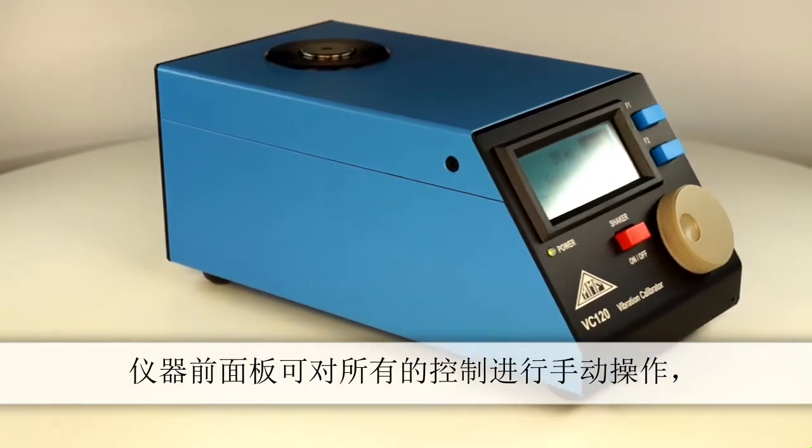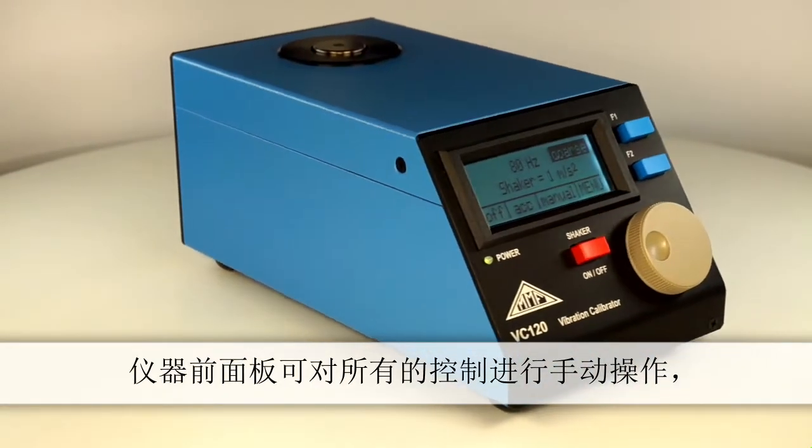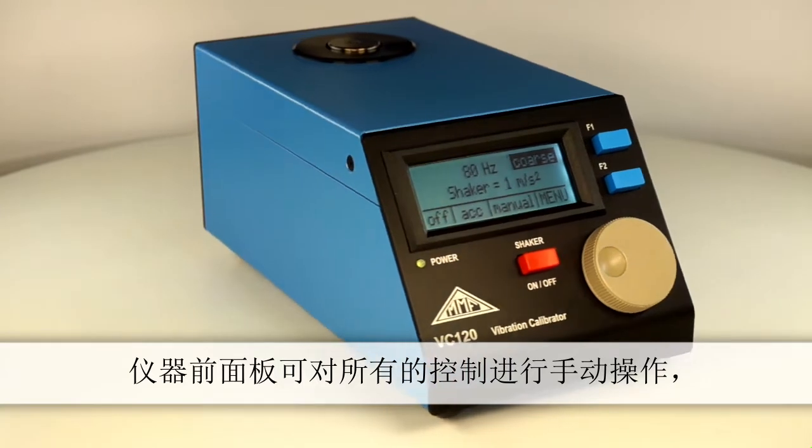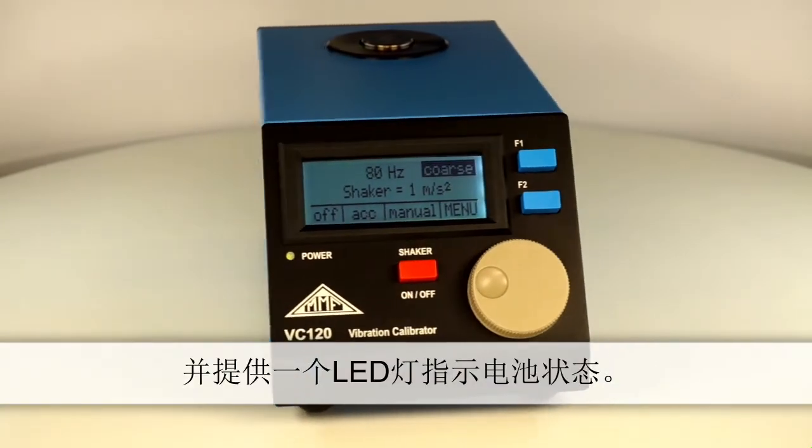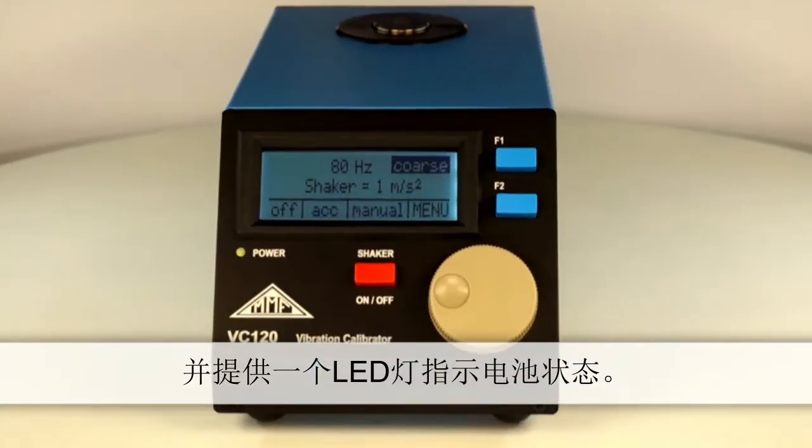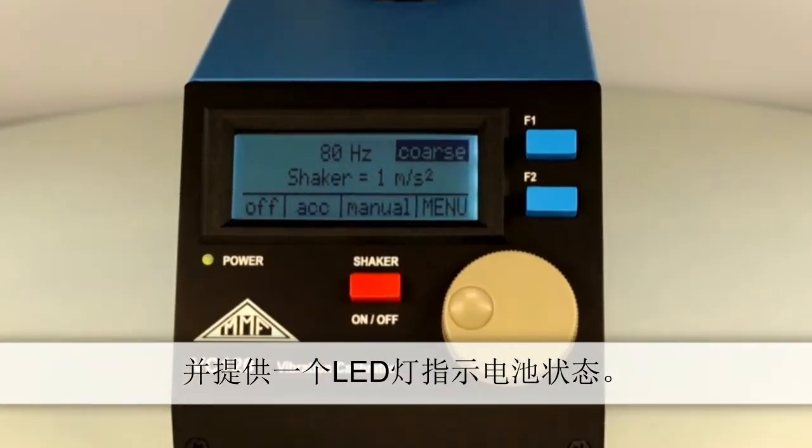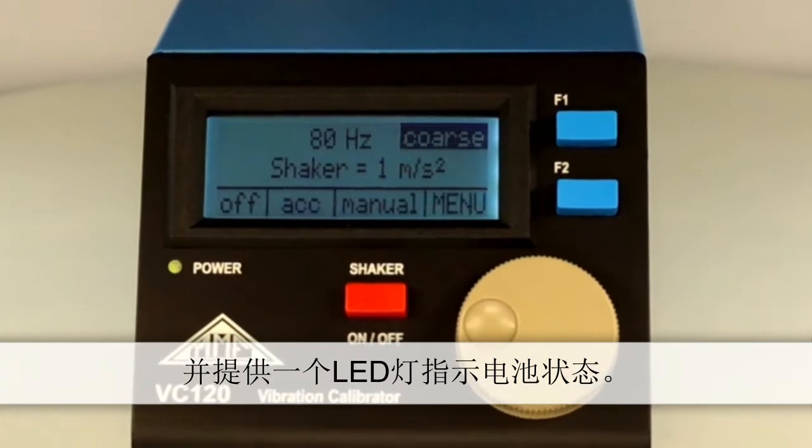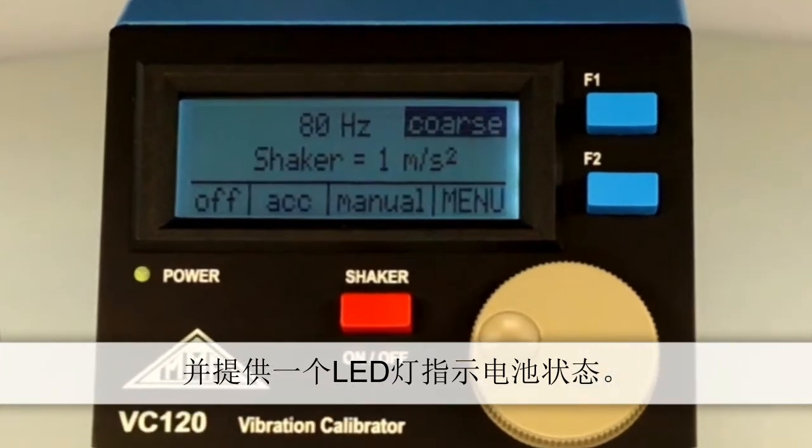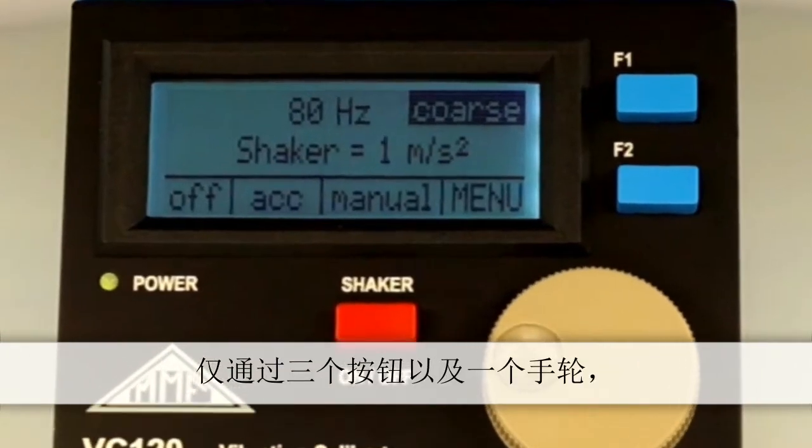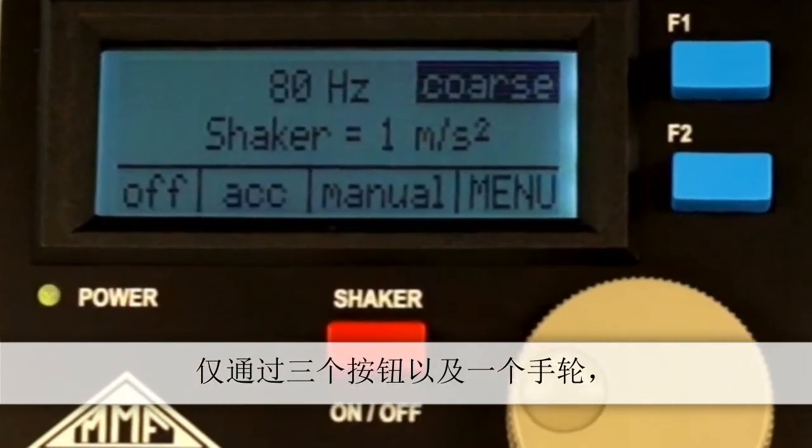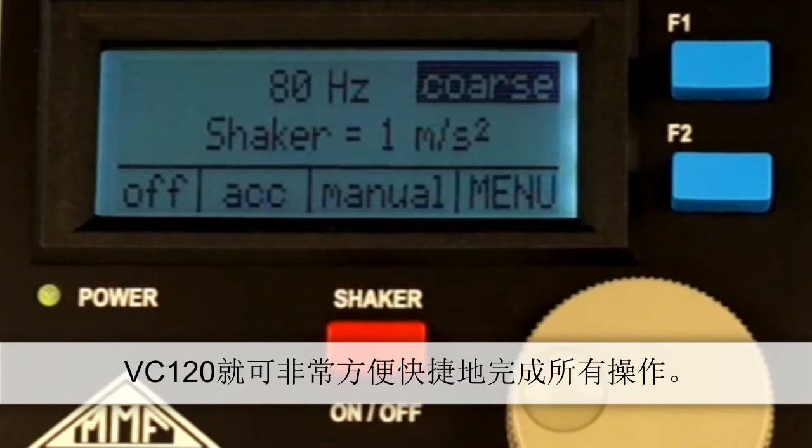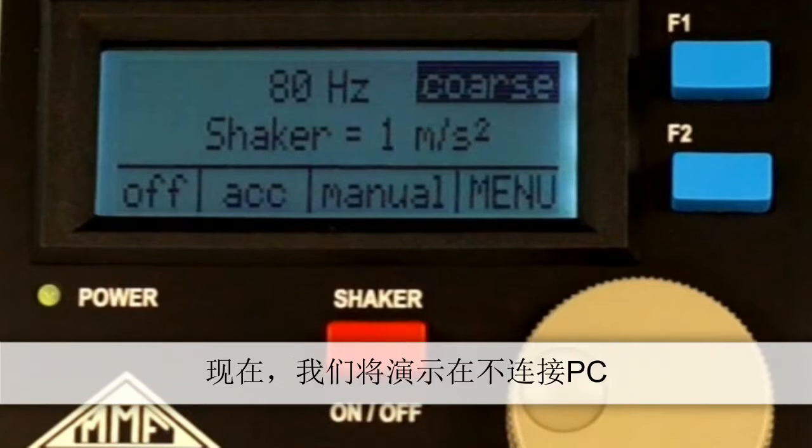The measured sensor sensitivity is shown on the LCD display at the front of the instrument. All other controls are located at the front, including an LED indicating battery operation. The instrument is simple and intuitive to operate using the three buttons and shuttle wheel.